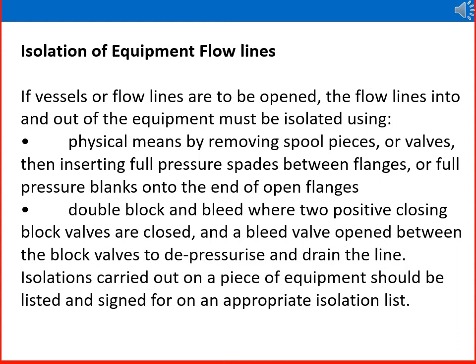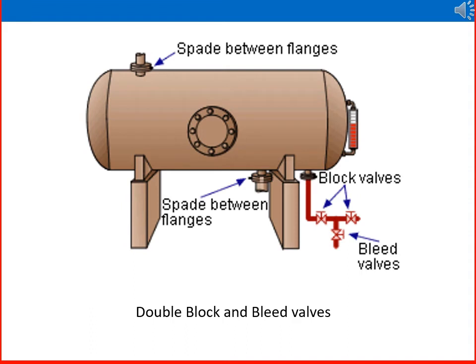For isolation of equipment flow lines, if a vessel or flow lines are to be opened, the flow lines into and out of the equipment must be isolated using physical means: by removing spool pieces or valves, then inserting full pressure spades between flanges or full pressure blanks onto the end of open flanges; or using double block and bleed, where two positive closing block valves are closed and a bleed valve is opened between the block valves to depressurize and drain the line. All isolation carried out should be listed and signed for on an appropriate isolation list.